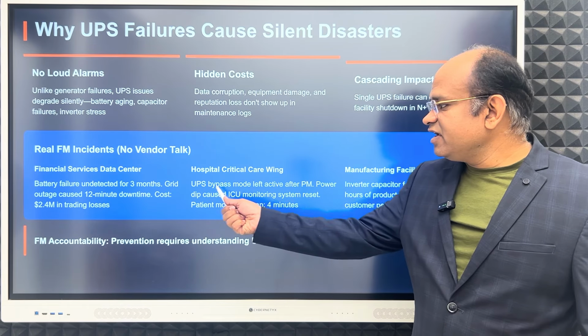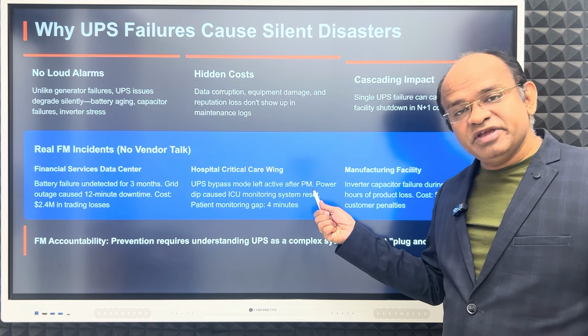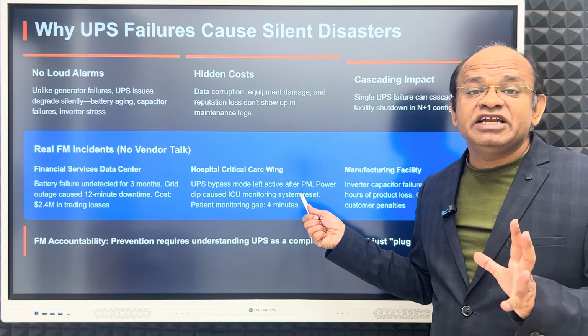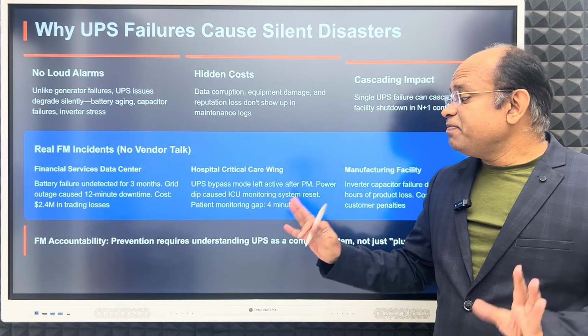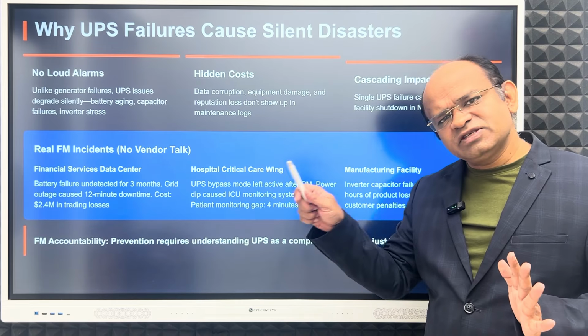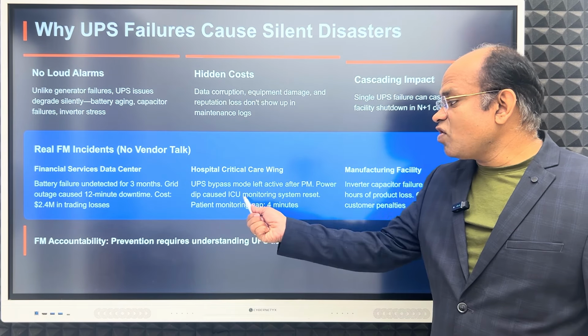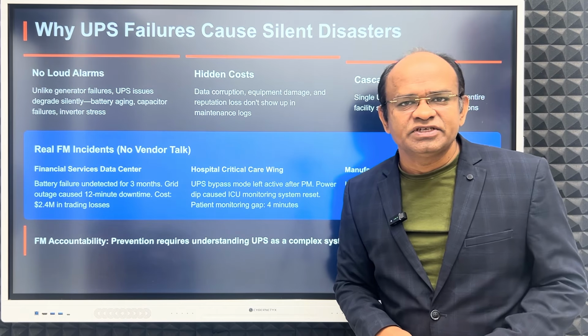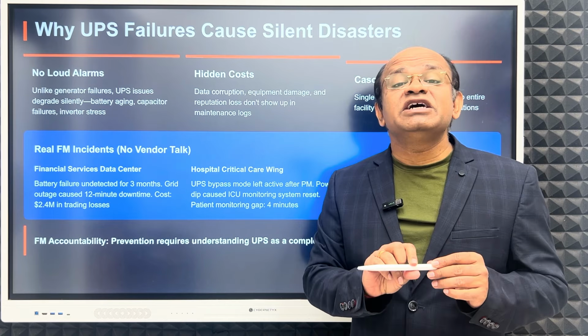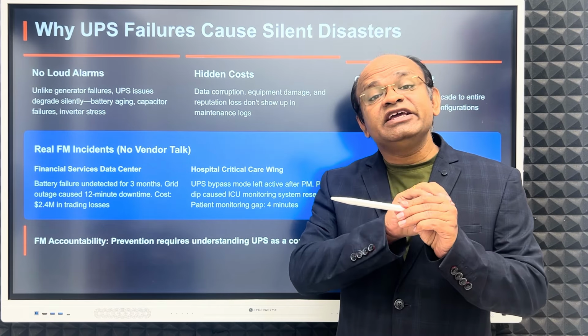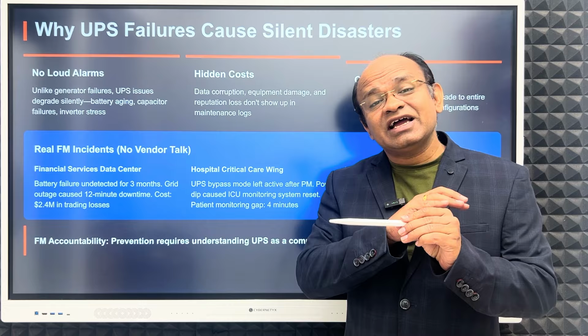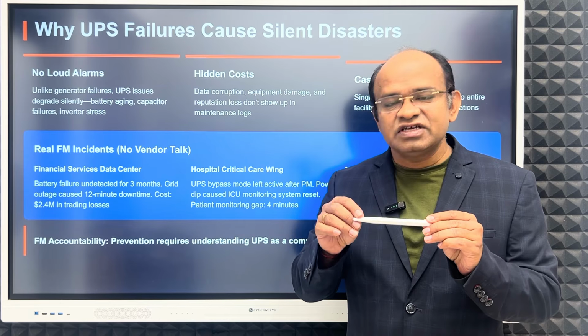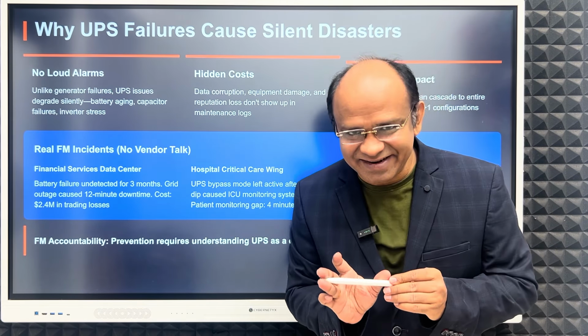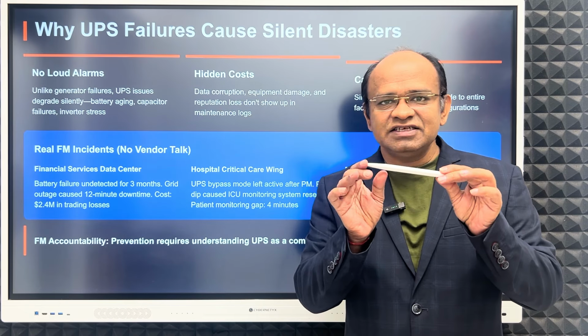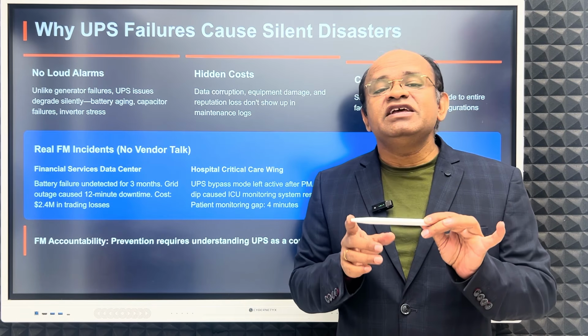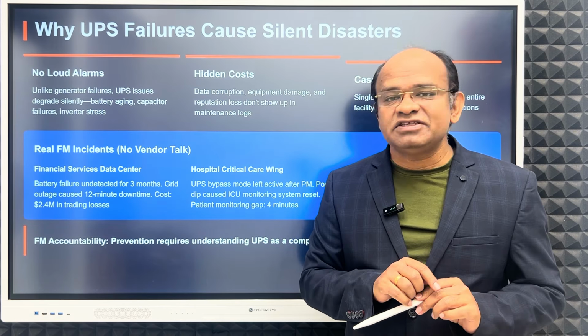In a hospital critical care wing, the UPS bypass mode was left active after preventive maintenance, so bypass was feeding the load directly. Then a power dip caused the ICU monitoring system to reset. This UPS conditions the power, whatever comes in, power sags, voltage sags, frequency variations, it purifies it. It's like a water purifier, but for power. If it's bypassed, this protection is gone.